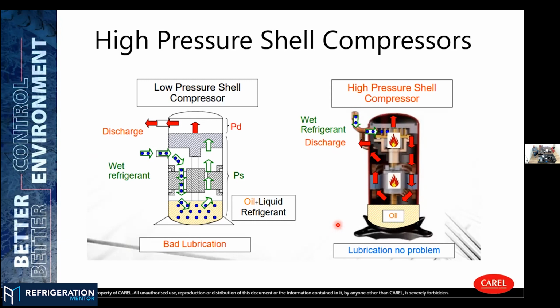So we have some protections inside the software that keep monitoring the discharge temperature. In case of higher discharge temperature, we decrease the speed of the compressor, reducing this temperature. In other cases, in some specific models of compressor, not for CO2, unfortunately, we can vapor inject some refrigerant inside the compressor in order to cool down the discharge temperature. So we keep monitoring, and we have thresholds where we first decrease the speed of the compressor, and if the temperature doesn't decrease at all, we stop the compressor in order to protect it.